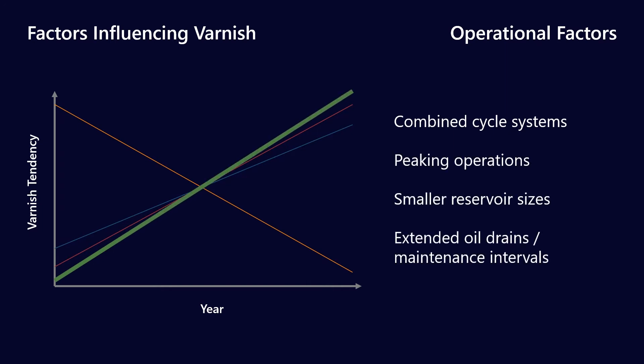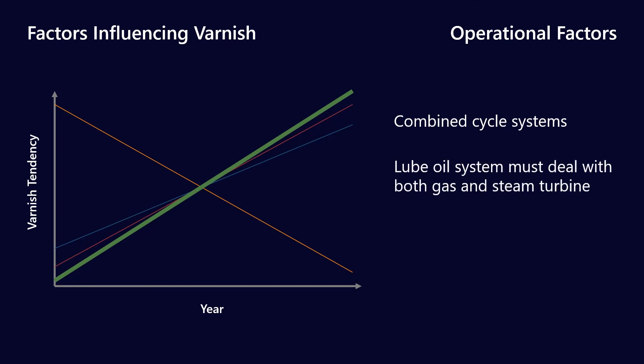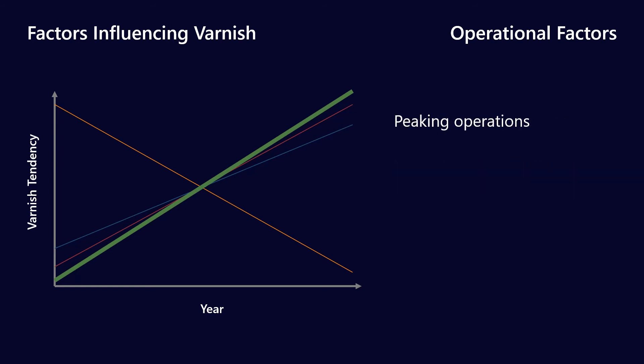We've also got operational factors — combined cycle systems, peaking operations, small reservoir sizes, and extended oil drains and maintenance intervals — all contributing to increased varnish tendency. With combined cycle systems, there's generally a shared lube oil system between the gas and steam turbine. The lubricant has to deal with more water than a standard gas turbine would, and it tends to get worked a little bit harder.